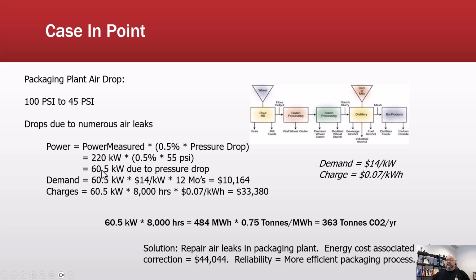So by addressing the leaks in the system, we can look at the total costs being in demand at $14 per kilowatt and 7 cents per kilowatt hour. Those numbers have changed dramatically recently, but that's neither here nor there for this presentation. But 60.5 kilowatts times $14 per kilowatt across 12 months, that's about 10 grand. And then if we take charges, which is our usage, that's 60.5, say we're operating 8,000 hours, at 7 cents per kilowatt hour, that's 33,000. So we're talking about $43,500 approximately, is what we're losing due to just air leaks.